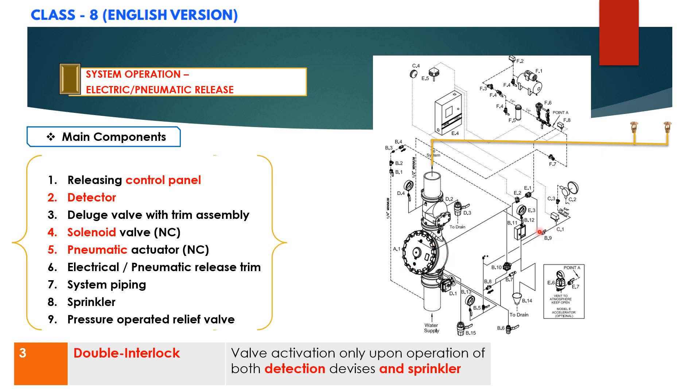then we have an emergency release B11 which can be pulled. Then the pressure is released from the priming chamber. As you can see this line, priming line is connected to the manual release. The pressure will be released through the priming line and it will flow to the drain point.